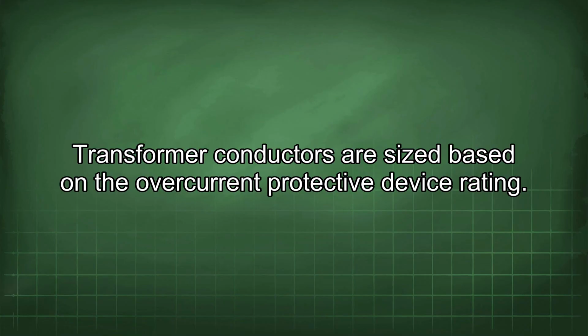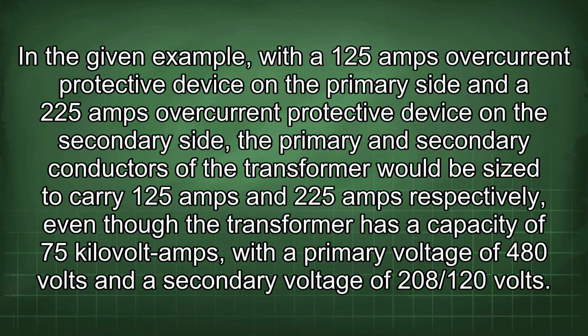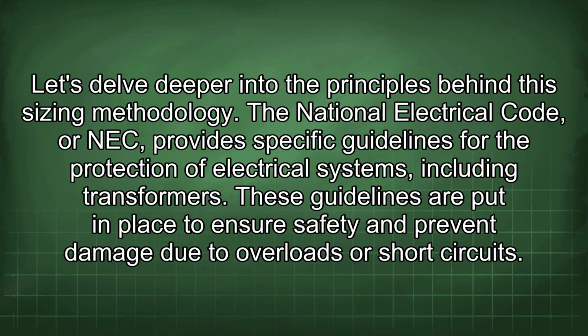Transformer conductors are sized based on the overcurrent protective device rating. In the given example, with a 125 amps overcurrent protective device on the primary side and a 225 amps overcurrent protective device on the secondary side, the primary and secondary conductors of the transformer would be sized to carry 125 amps and 225 amps respectively, even though the transformer has a capacity of 75 kilovolt amps, with a primary voltage of 480 volts and a secondary voltage of 208/120 volts. Let's delve deeper into the principles behind the sizing methodology.